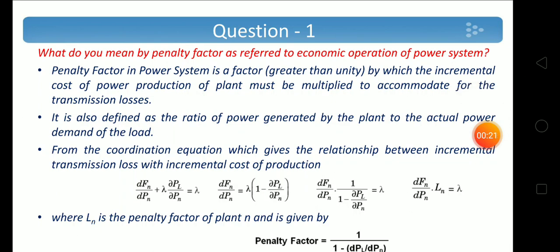First question: What do you mean by penalty factor as referred to economic operation of power system? We know that in economic dispatch neglecting the losses, the condition is the incremental fuel cost dF_n/dP_n equal to lambda. And when we are considering the losses in the economic dispatch problem including losses, we have to multiply dF_n/dP_n with a factor to get equal to lambda.